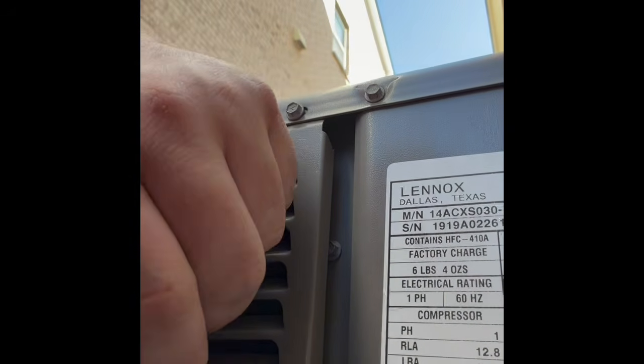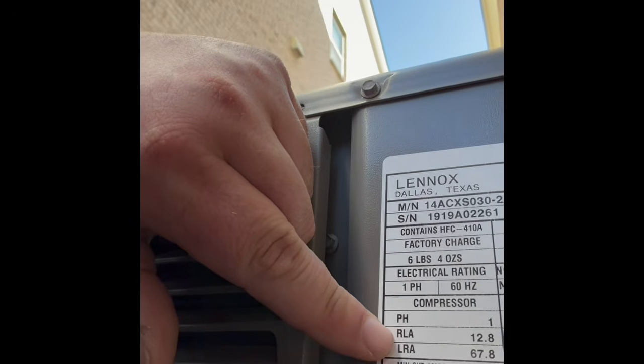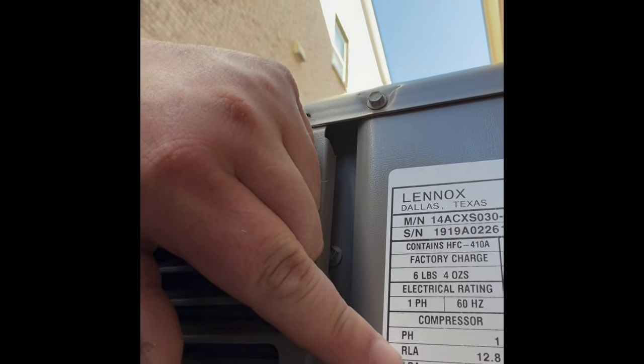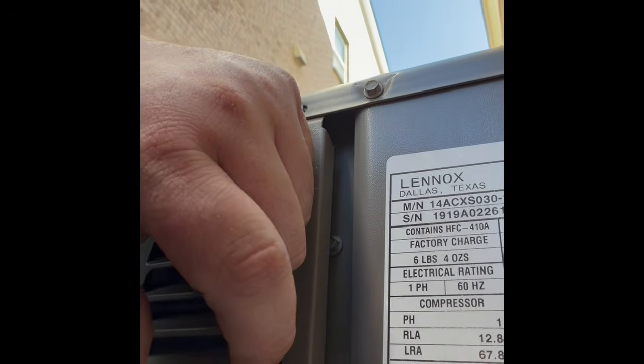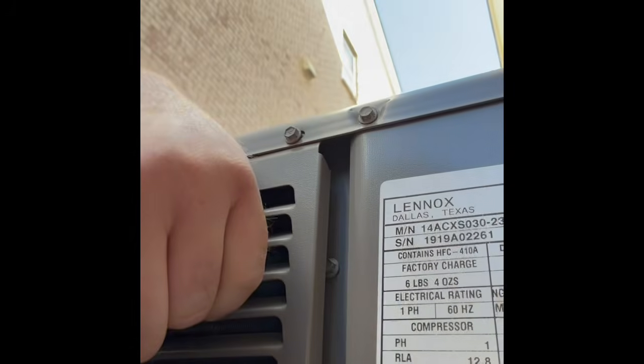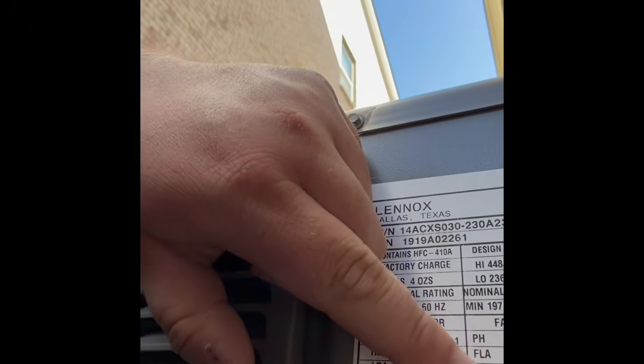So today I'm going to be checking our compressor amps. Right here we can find that we have the RLA. That's our 12.8. We want to see somewhere around that 6 mark is what we're going to be looking for today. Right here's our fan motor amps. It's about 1. We're going to be looking for about 0.5 to 0.6 today. We're also going to test the capacitor as well as the contactor.